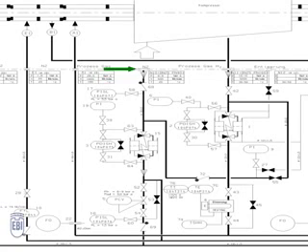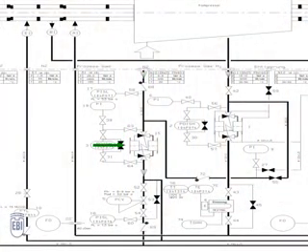To pressurize the seal with gas, nitrogen is taken from the nitrogen network of the plant. If the nitrogen supply is not stable, we recommend a backup by means of a nitrogen tank. Should the nitrogen be neither clean nor dry, we recommend a dual filter system with coalescer elements as installed in the gas supply of the primary seal.